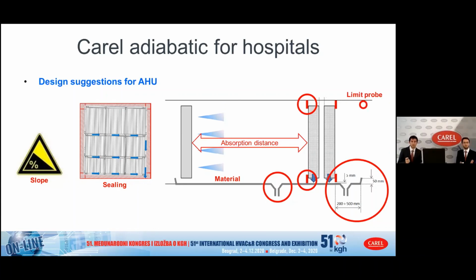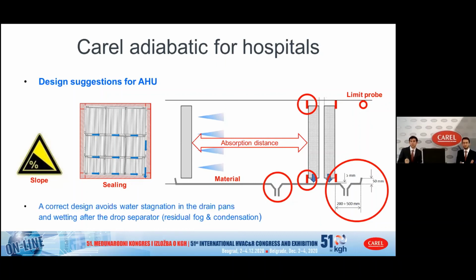In the end, just to remind you, there is the limit probe that must be installed at the end of the system, after the drop separator, to avoid the relative humidity growing over 80%, usually. So a correct design avoids troubles in the air handling unit, especially residual fog condensation after this section.